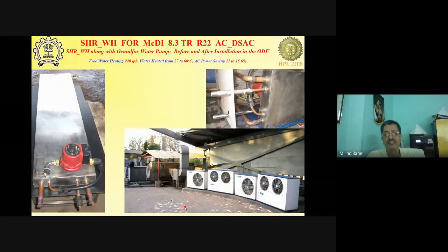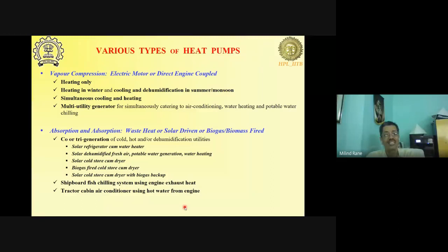Later on, they deployed a total of around 340 units in various McDonald's outlets, at the time when all the McDonald's outlets in the south and western zone were fitted with our unit. So, various types of heat pumps, if we were to quickly review: heating only, heating in winter, cooling and dehumidification in summer, or simultaneous cooling and heating, and multi-utility, which can simultaneously cater to cooling, water heating, potable water chilling, and so on. And now what we have graduated to is a multi-utility generator with flexibility in tapping the utility.